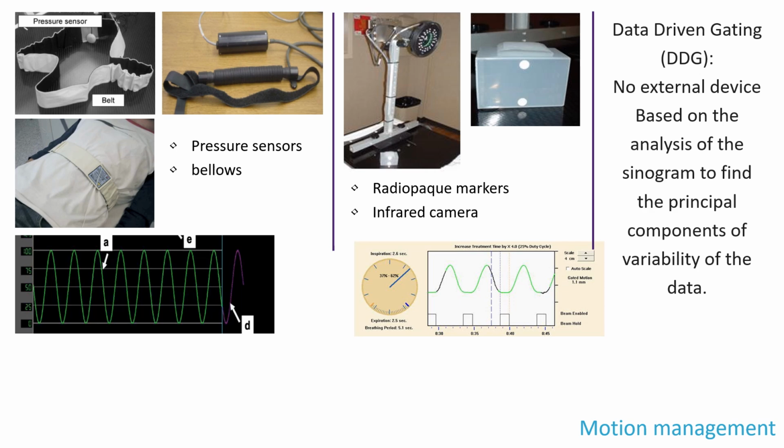To perform 4D acquisition, we need a system to trigger the breathing of the patient, a system that records a change that corresponds to a specific phase in the breathing cycles. Trigger systems can be, for example, a belt that records a change in pressure during the movement of the patient thorax.